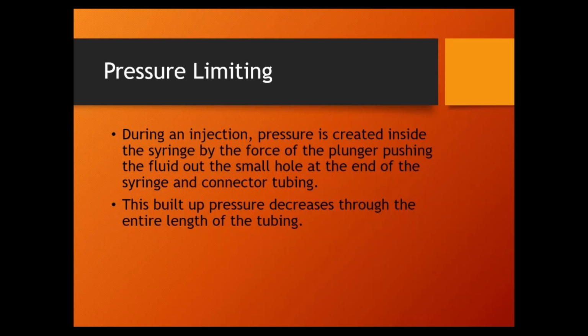All right, so what happens? The injector doesn't stop. So let's say we set the pressure limit to 600 PSI. We're doing the injection, and my injector system says I hit 600 PSI in the syringe. If it doesn't stop, what does it do to keep pressure from going up and up and up? Slows down. It's going to slow the flow rate down.